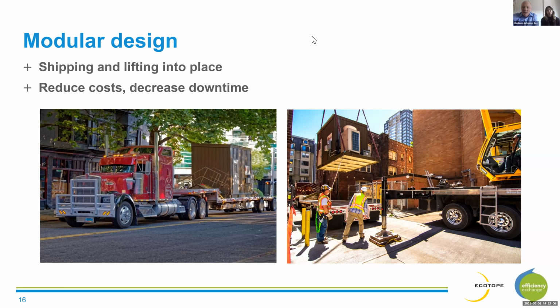The other thing I would say about it is that by coming together as a single package system, you now have one place to go for warranty issues. Everything was supplied by the same person, instead of a mechanical engineer specifying the heat pumps from one source, the tanks from another source, potentially the control system from another source, putting it all together on site, or a contractor puts it together on site based on the engineer's design, and then some maintenance person comes and decides that a valve should be in a different position. There are a lot of ways that site-built systems can go wrong that this addresses, so it significantly reduces the risk of this type of new technology.